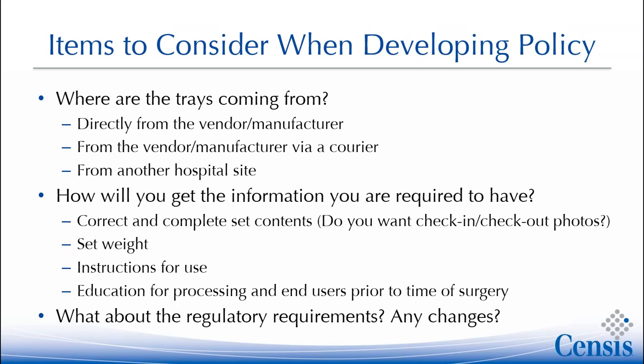You need to set the weight on these trays, and there's a lot of loaner trays out there that still weigh in the neighborhood of 50 to 60 pounds. You need to get the set down to 25 pounds. Now, you can't just start doing that on your own, because the manufacturer has validated his process and instructions for use. However, we do have gold standards established by AORN and by AAMI that say 25 pounds is the max weight that we can possibly sterilize this tray.